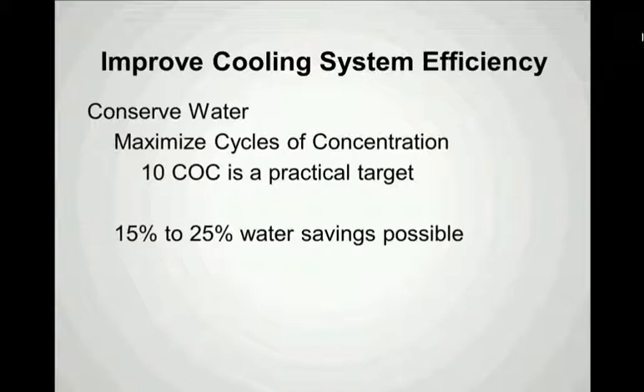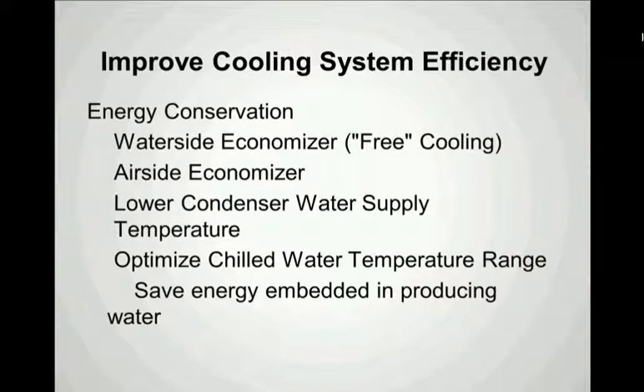We also want to operate with good energy efficiency, and there are several strategies for improving it. One is to make best use of a water economizer or free cooling heat exchanger. This takes the chiller out of service and saves the energy that would normally be used to drive the chiller compressor.